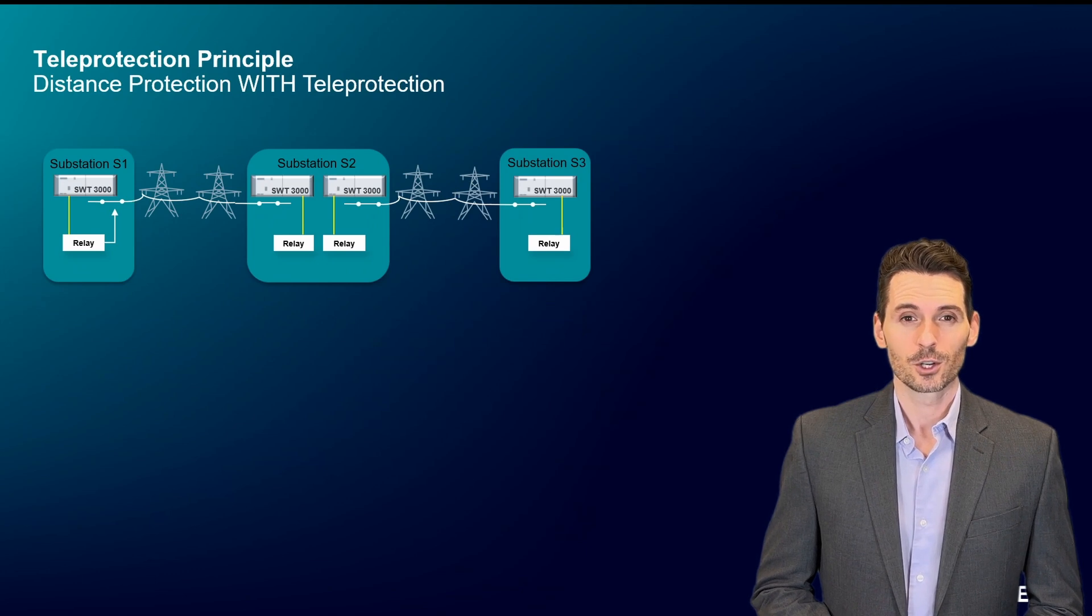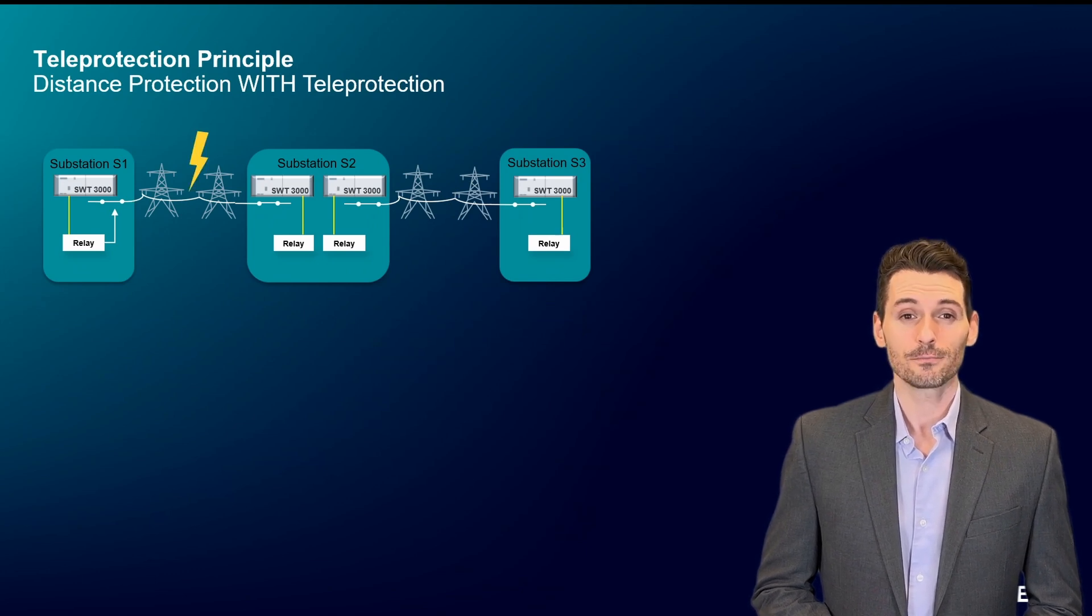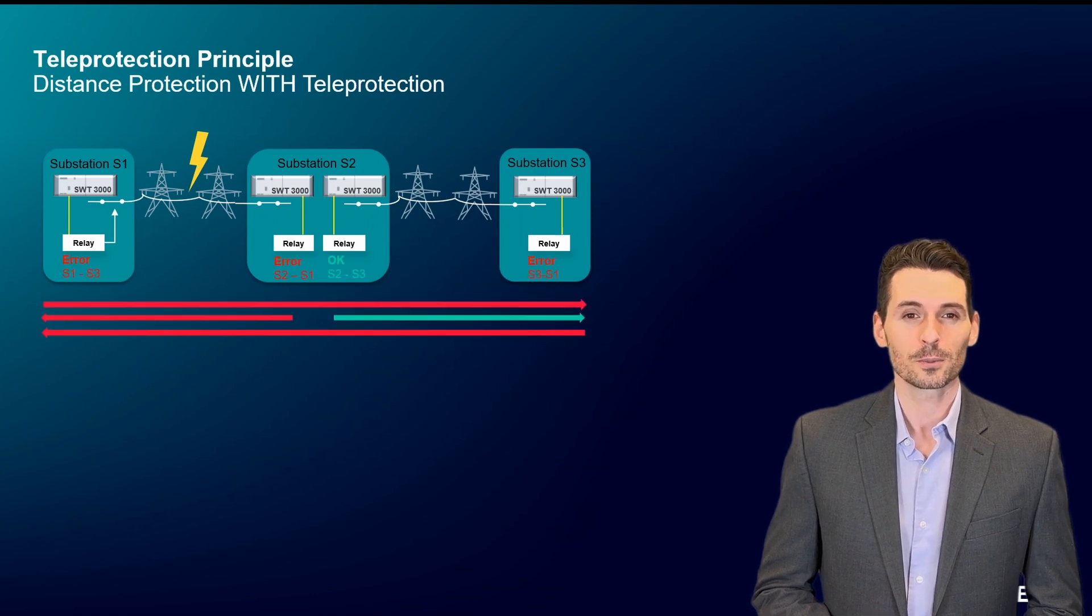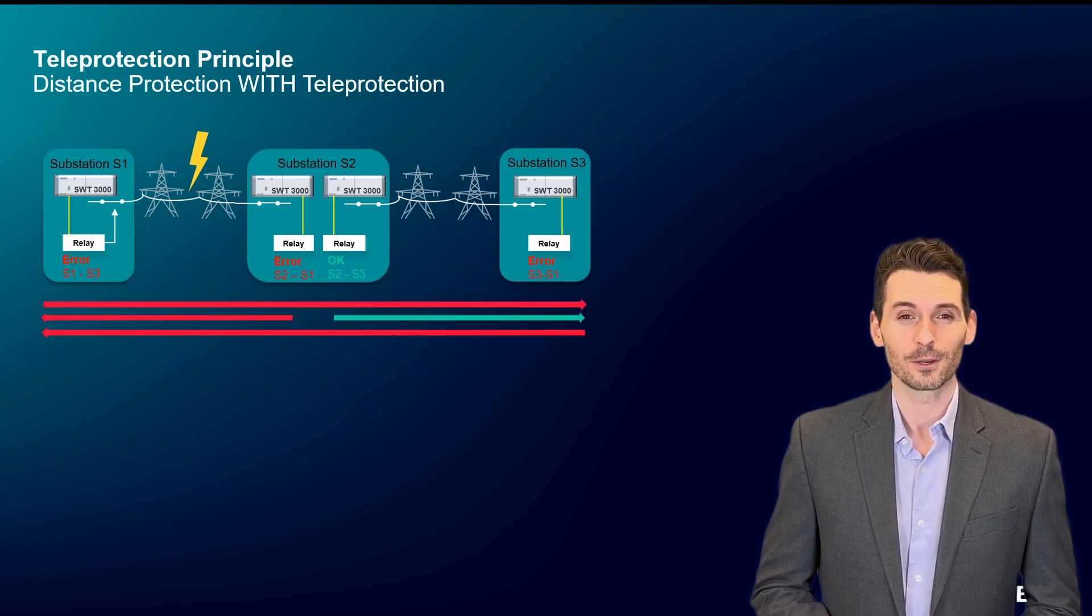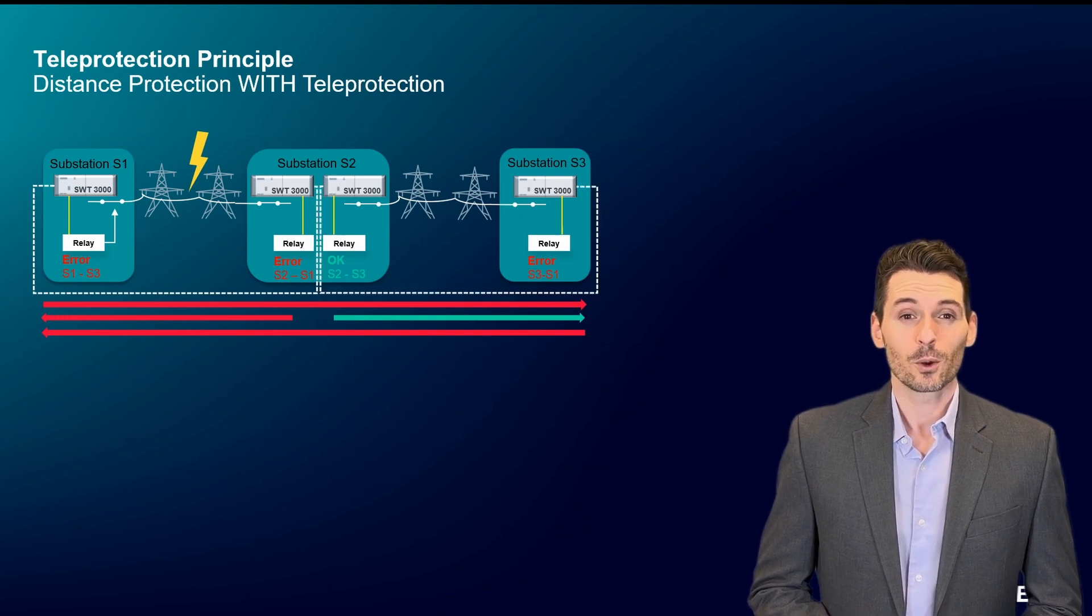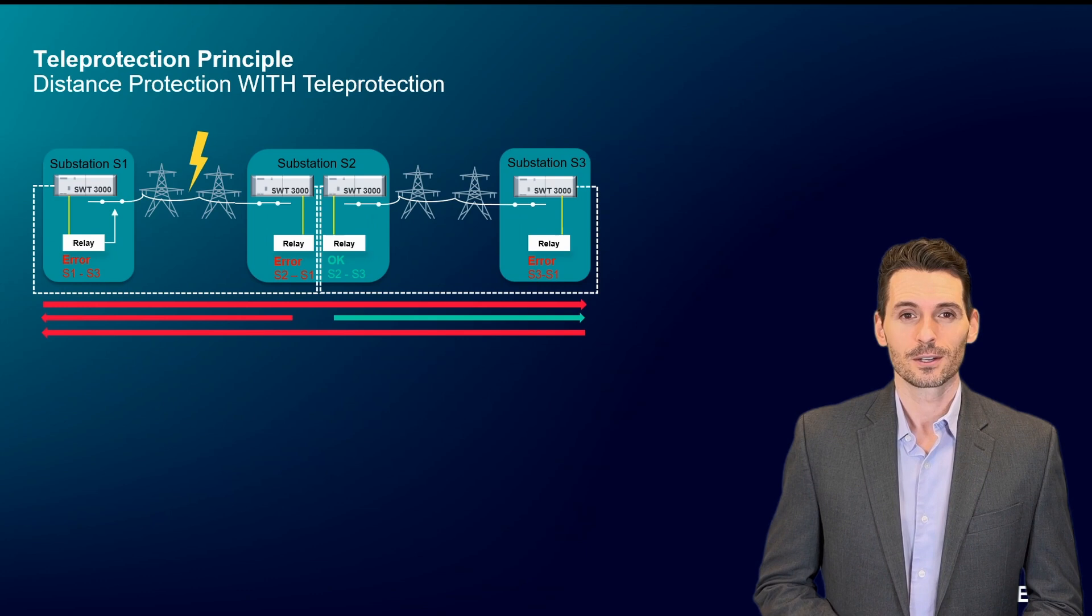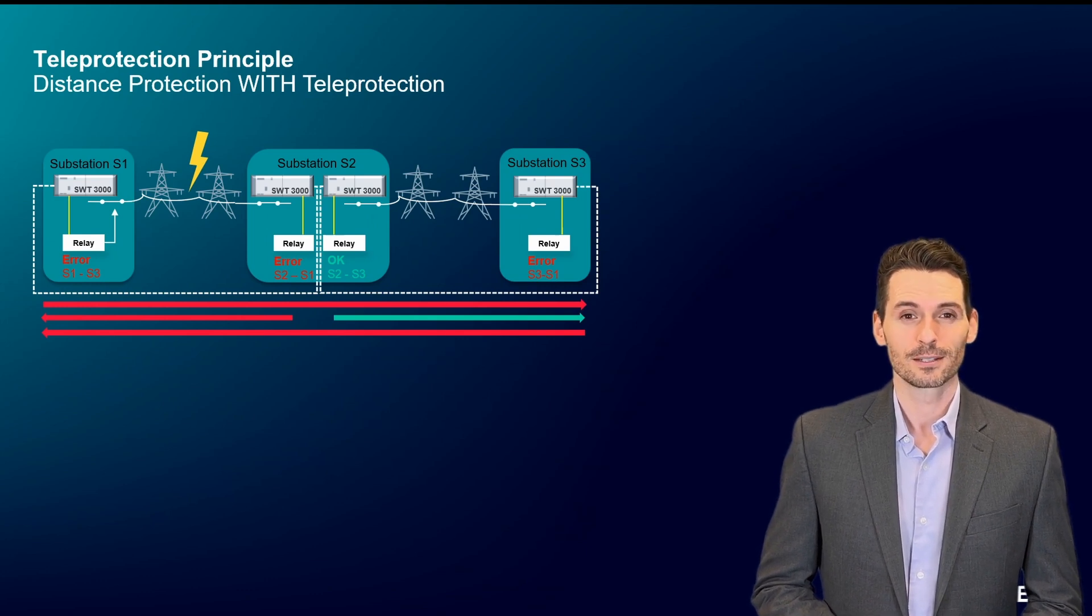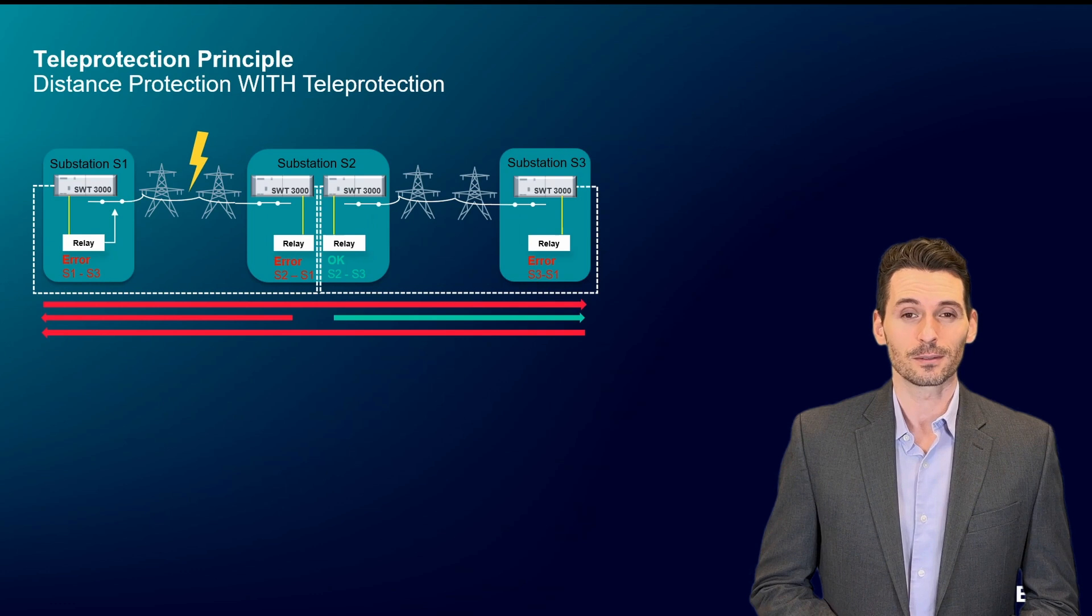The situation is the same as before. A fault occurs between substations 1 and 2. The distance protection relays detect the same error scheme as before. This time the failure is communicated from the relay to the protection signaling system. The two corresponding protection signaling systems communicate with each other.